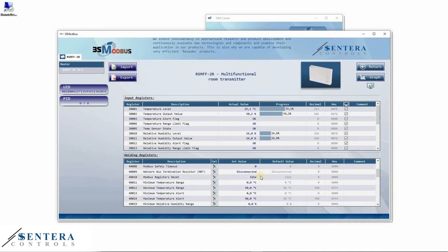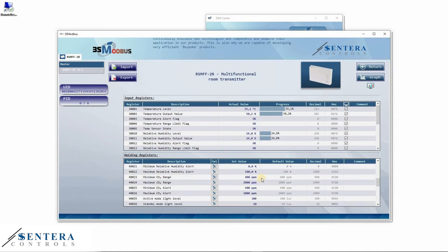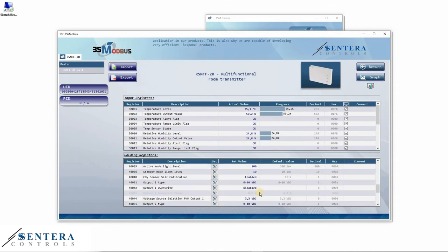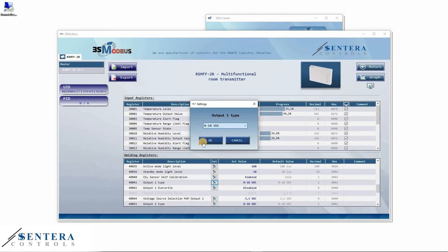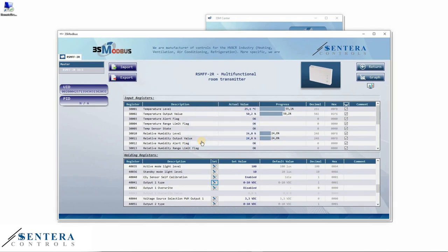What is more, you can easily rely on the product default settings and use them without the need of any further adjustments. For example, a sensor type can be set to 0 to 10 volts, which is the default value, 0 to 20 mA, or 0 to 100% PWM. For personalized Modbus RTU settings, you have unlimited access to Sentera's user-friendly software.